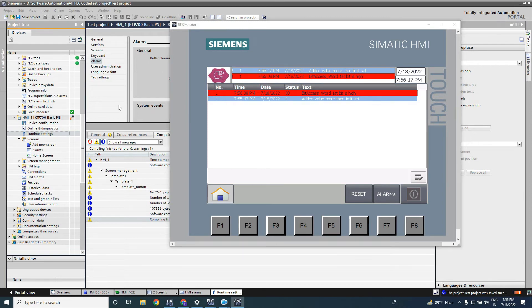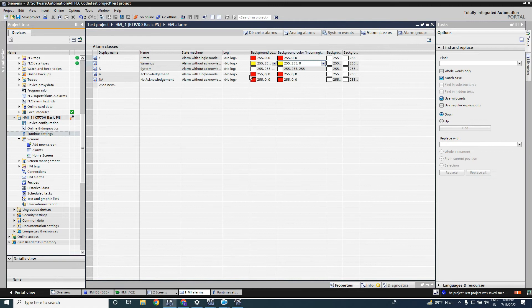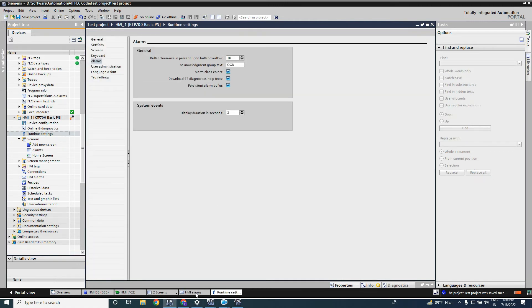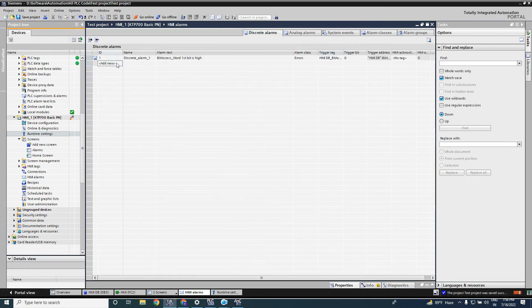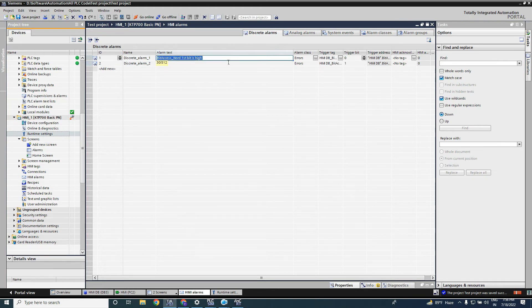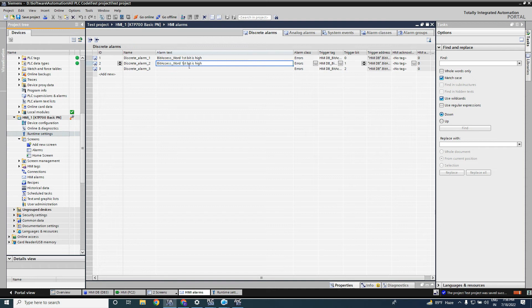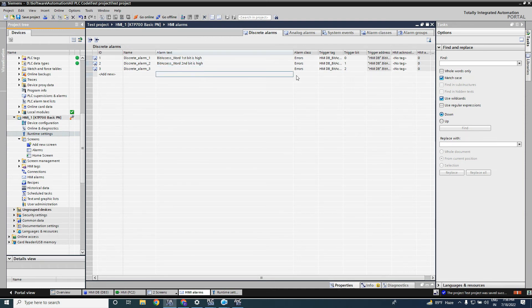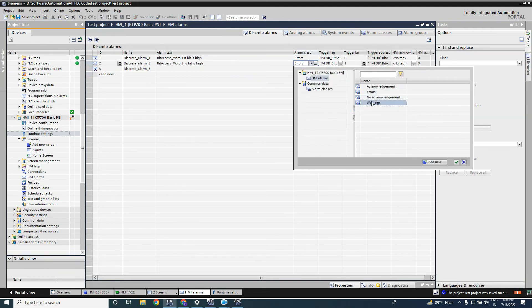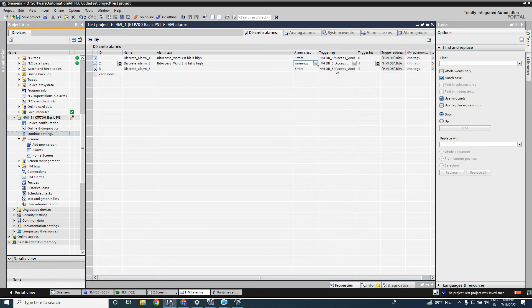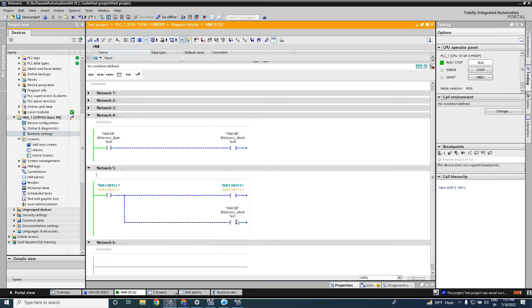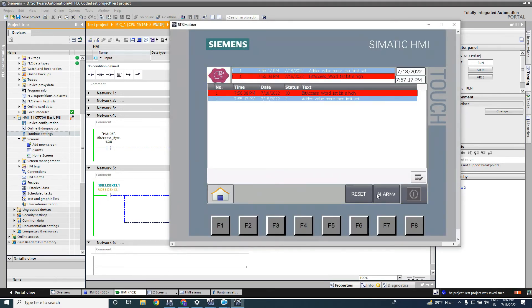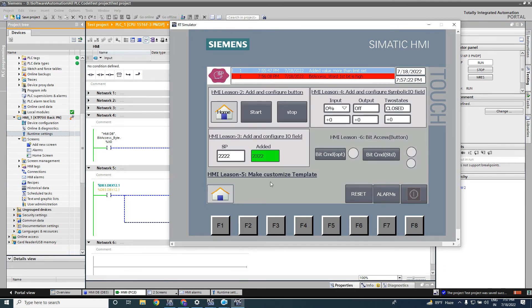Now if I give a command, you can see the alarm color is red. If you want to see the yellow warning alarm, you have to make a warning alarm. Click add alarm, configure the second bit: 'second bit is high', and select it as a warning alarm. The tag number is the same — bit access word — and the trigger bit is one.